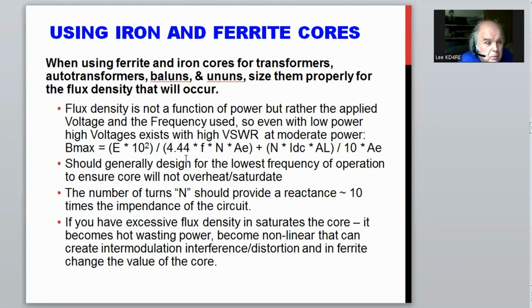So when we design the core and want to size it properly, we need to design for the lowest frequency of operation to ensure the core will not overheat and saturate. The number of turns we use for our transformer should provide a reactance of about 10 times the impedance of the circuit - that's the general rule of thumb.